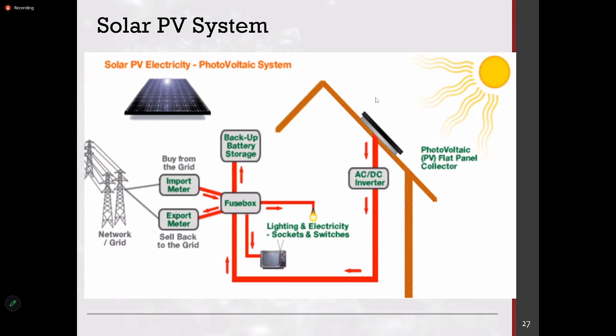But now what we call an on-grid system is where you invert from the inverter, and it will first supply the residence, because that is the shortest path and lowest resistance path. So your inside residence load will be supplied, and whatever extra there is will get exported. You're supplying to the national grid.